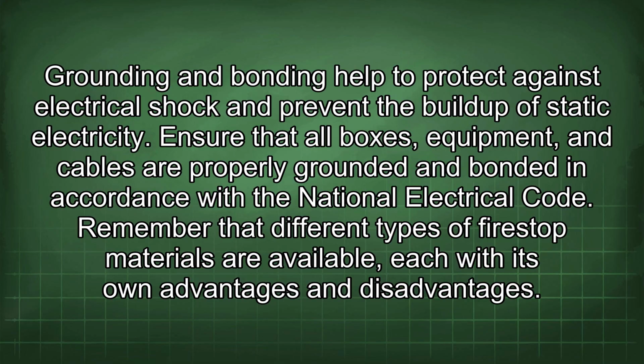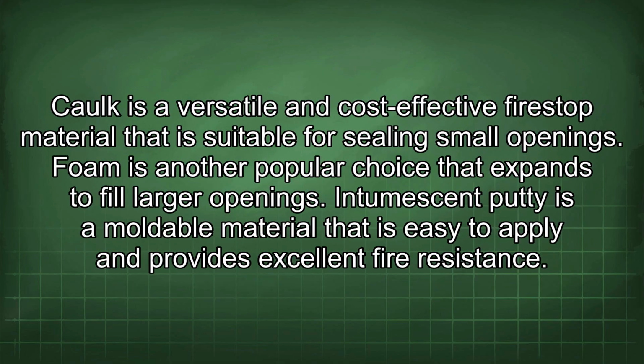Ensure that all boxes, equipment, and cables are properly grounded and bonded in accordance with the National Electrical Code. Remember that different types of fire stop materials are available, each with its own advantages and disadvantages. Caulk is a versatile and cost-effective fire stop material that is suitable for sealing small openings. Foam is another popular choice that expands to fill larger openings. Intumescent putty is a moldable material that is easy to apply and provides excellent fire resistance.